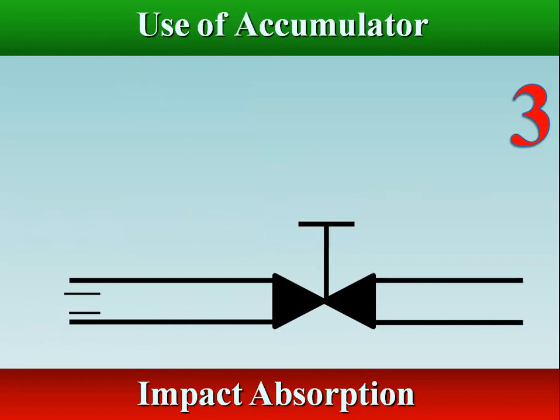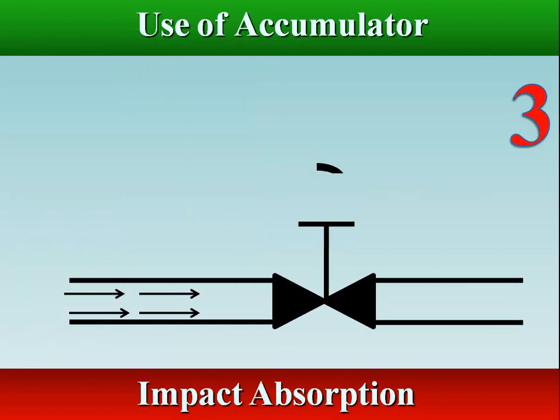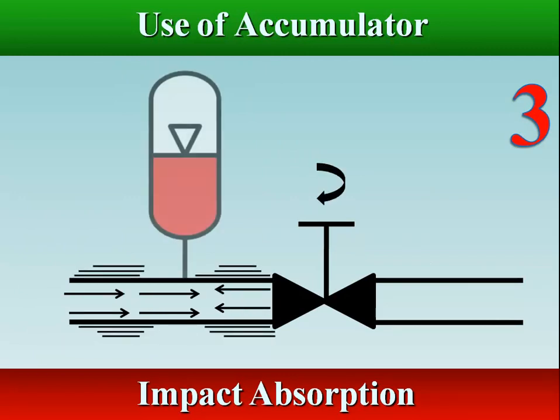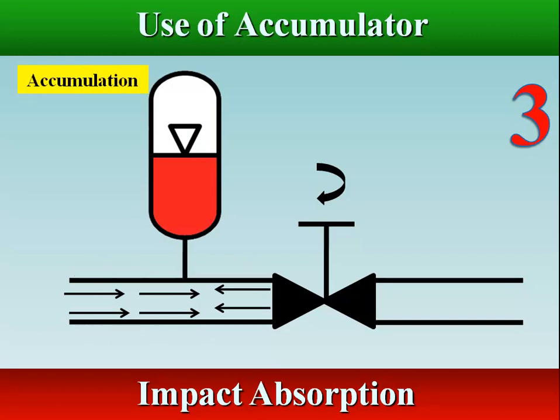The rapid closure of valves or sudden changes in load within a hydraulic circuit can result in impact pressure in pipes, which can then lead to noise or damage to those pipes or devices. The use of an accumulator can mitigate any such internal shock.